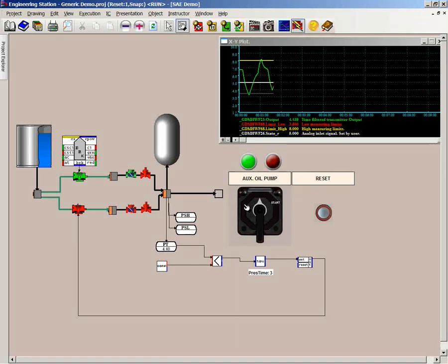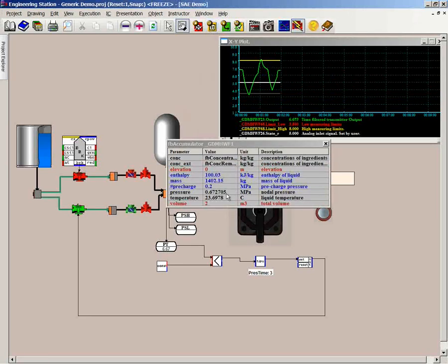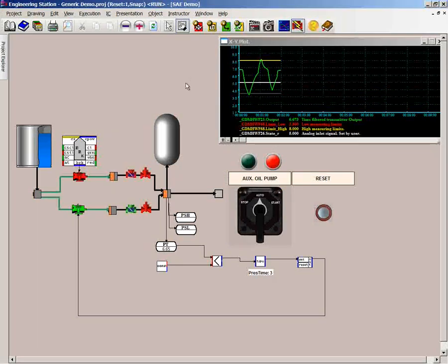Now, we will again reset the system, restarting the first pump and stopping and rearming the standby. Next, we will observe the effect of reducing the size of the accumulator in the system, effectively reducing the overall capacity. This could be due to design considerations, either of cost or simply of having only a certain volume or space in which to fit the accumulator.